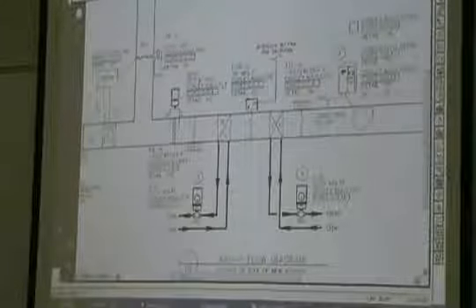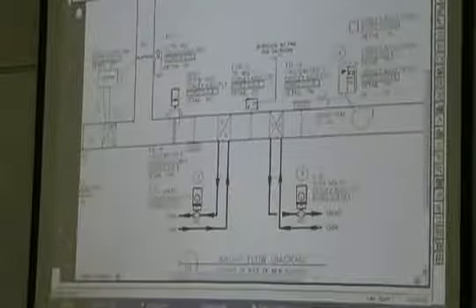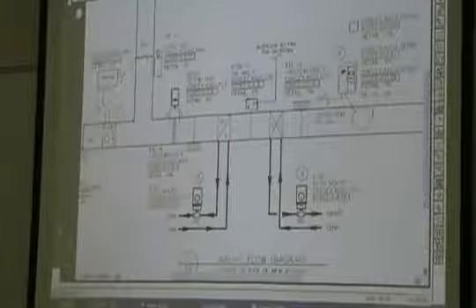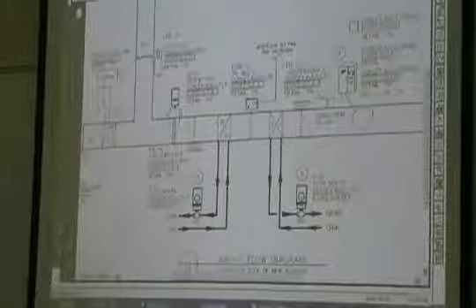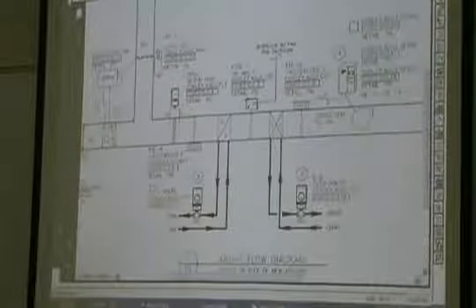Again, all he's saying is that if this damper is not fully open, I don't want to be doing any mechanical cooling. Okay? Make sure that this is in the sequence. Make sure that this damper, the outdoor air damper, is wide open before we start using the chilled water coil. Why don't they make it that easy and just say that?